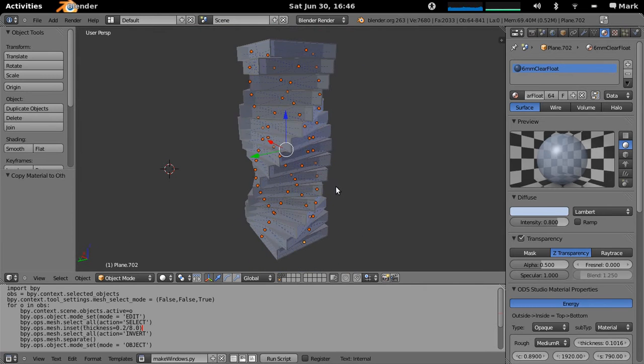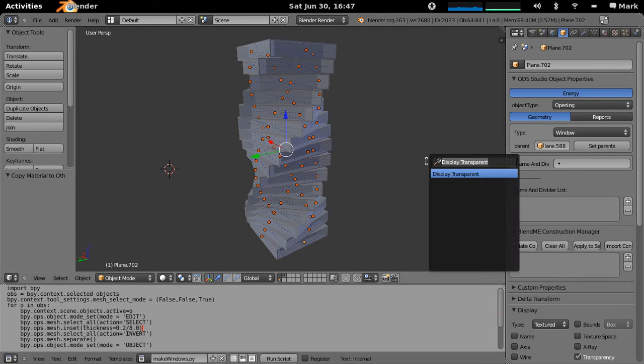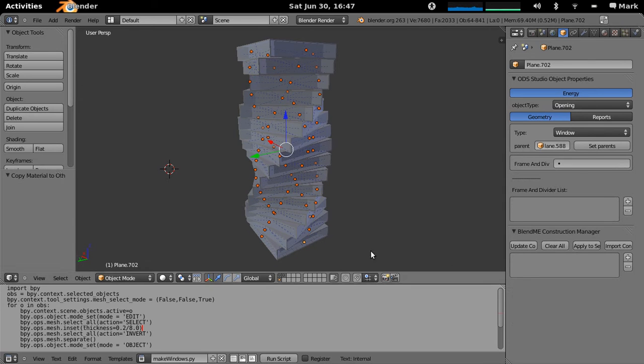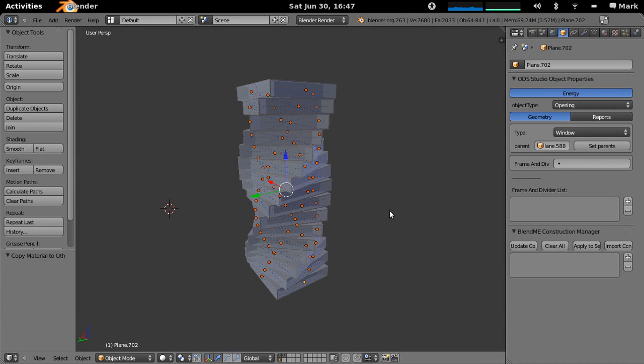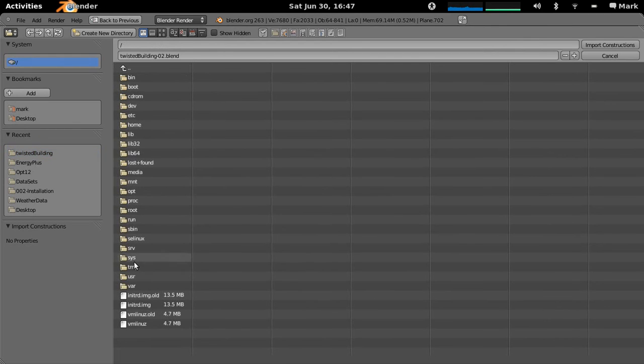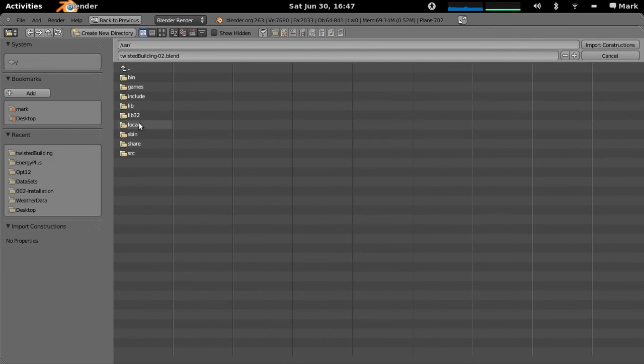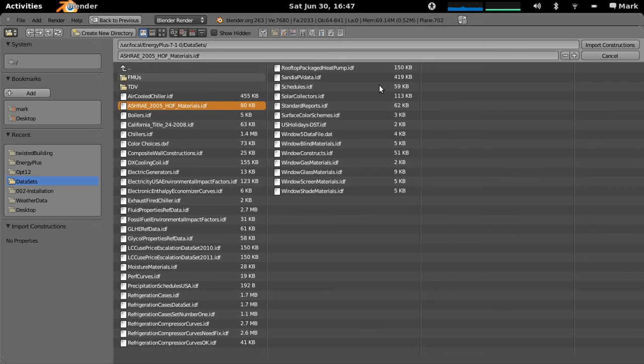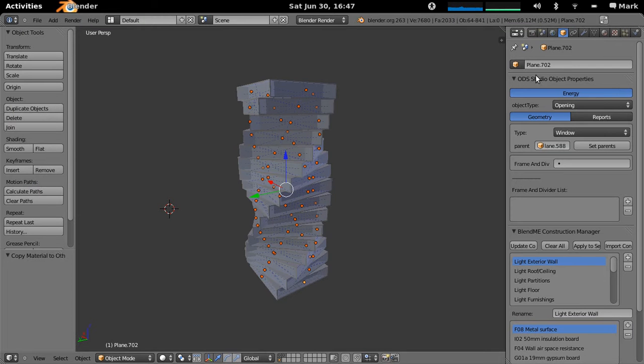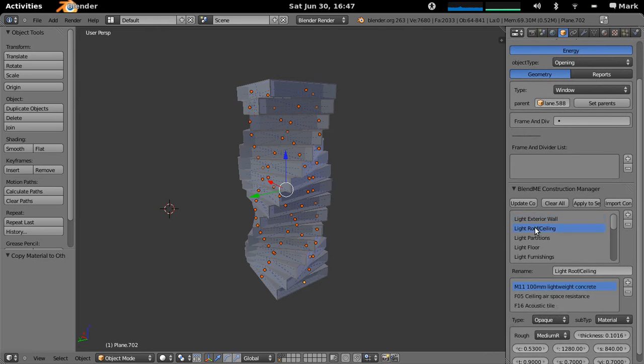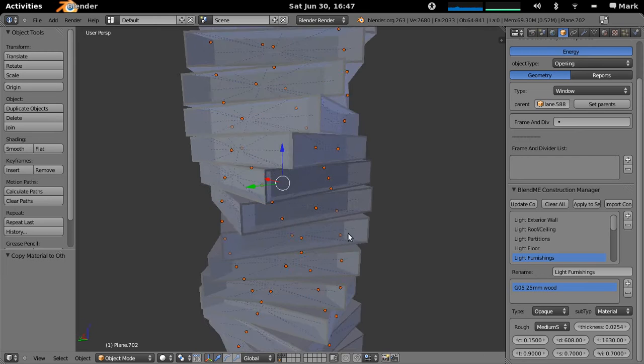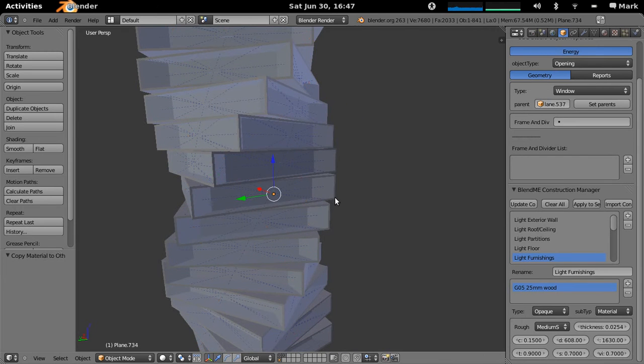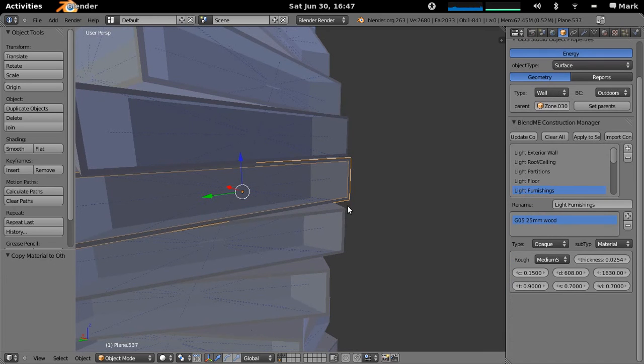To get the proper model running you'd still want to actually apply some materials to this. And this is where in the new ODS version 0.6 we actually have this construction manager here. So I'll just actually clean up the interface because you don't want to see all these other menus. And what you can see here is we've actually got a construction manager and there's a button here that says import constructions. And you can actually just go to wherever your Energy Plus is installed. It's normally user local Energy Plus data sets. And you can bring in the ASHRAE 2005 Handbook of Fundamentals materials. So you can import any IDF and it will bring in all of the materials from there. So there's all your constructions ready to go.